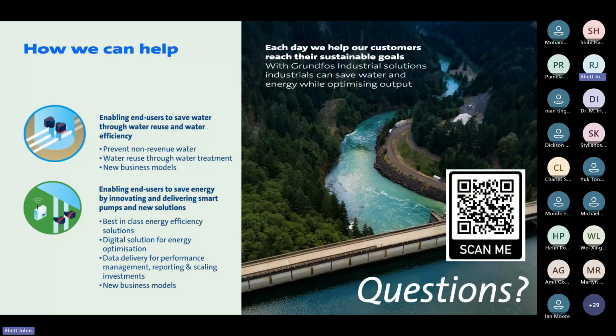Generally, wastewater systems aren't going to have the biggest energy savings because they're not necessarily going to be running all the time, and the requirements and the changes aren't that large. But if you want to resize your system, it starts with understanding how it's operating. And then, if you find that the pump is oversized, you would simply resize the pump downwards. And even reducing the size of the pump and putting it such that it operates at a better efficiency point, that's going to give you savings on its own.